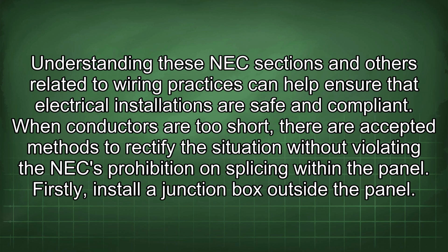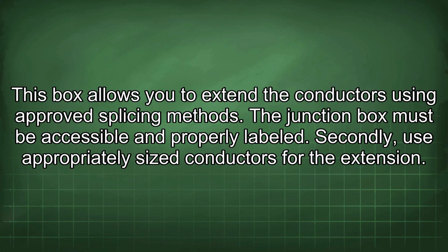When conductors are too short, there are accepted methods to rectify the situation without violating the NEC prohibition on splicing within the panel. Firstly, install a junction box outside the panel. This box allows you to extend the conductors using approved splicing methods. The junction box must be accessible and properly labeled.